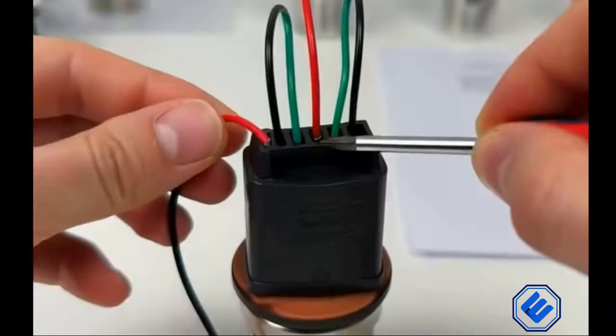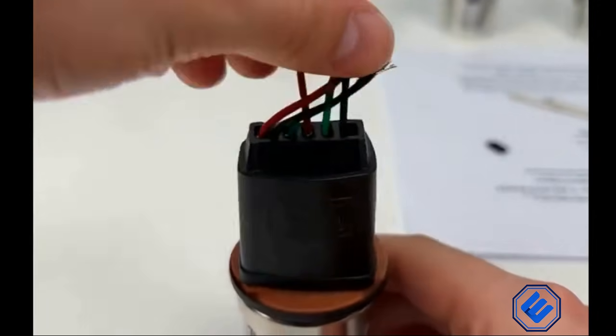We'll cover how to wire temperature and pressure sensors the right way, the biggest wiring mistakes that cause bad readings, and a simple maintenance checklist that prevents most failures before they happen. Let's get into it. Reliable sensor data is the foundation of everything: industrial systems, HVAC, automation, you name it. If your system can't trust its temperature or pressure readings, it's flying blind. Bad data leads to bad product quality, unexpected shutdowns, and hours of troubleshooting you'll never get back.